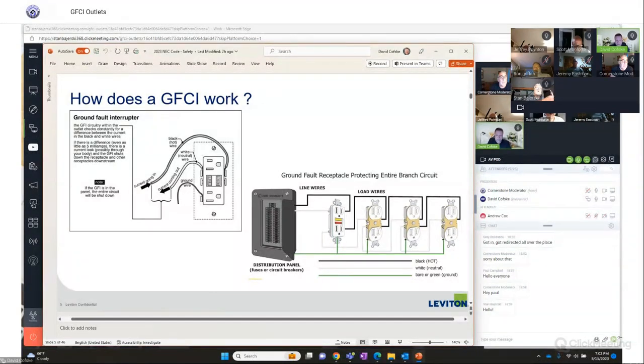Moving real quickly into what a ground fault is. A GFCI stands for ground fault circuit interrupter, and what it does is measure the current coming into the device and going out, and monitor that for a difference in current. GFCIs are a UL 943 device, and those are all required to be at a 5 milliamp trip to protect people. As soon as the device sees a difference between the incoming and outgoing current to ground, it will open up and trip. That's what it is intended to do. It's a safety device, and it's to protect against shock.